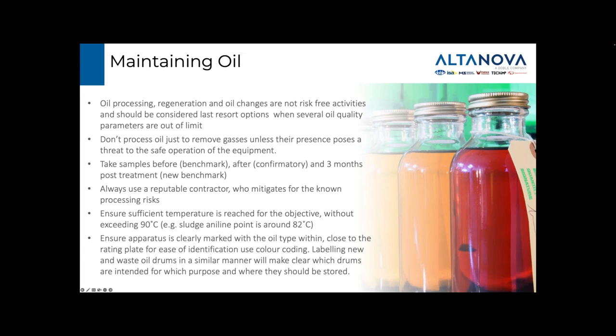At some point in a transformer's lifetime, intervention is more than likely going to be needed. However frequent this intervention will be required is dependent on how the transformer has been operated during its lifetime. The more stress it's seen in service, or the more moisture or oxygen that's present, then the quicker the oil will degrade and more losses will ensue. To combat this, there are a number of options like oil regeneration and oil changes. However, don't be tempted to process the oil regularly or just for DGA gas reduction unless the amount of gas present poses a risk to the asset. We need this data to accumulate over time to form trend analysis, and once we remove it via regeneration, it's lost. Oil maintenance is also not a magic bullet, and it's not risk-free.